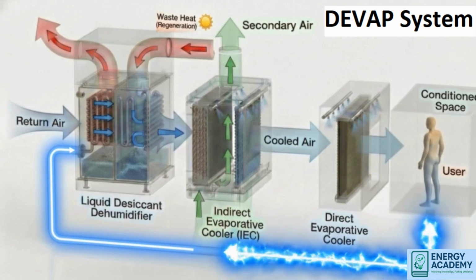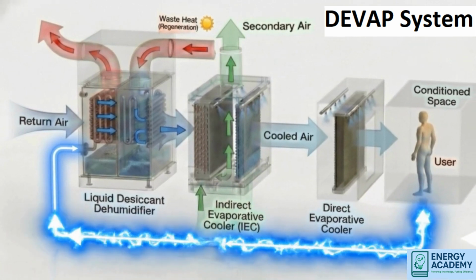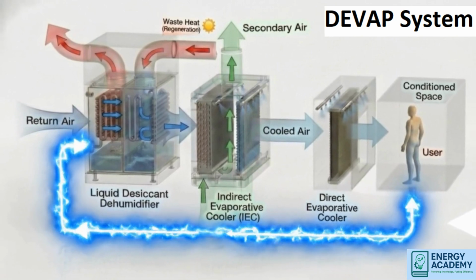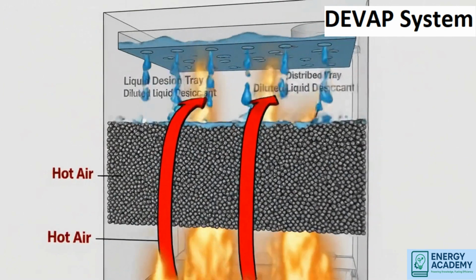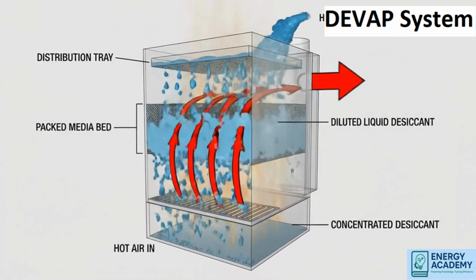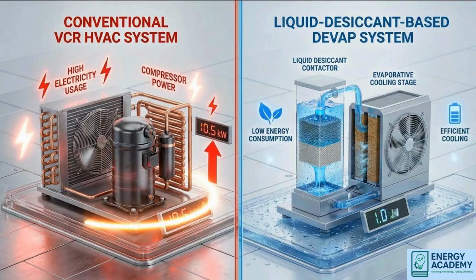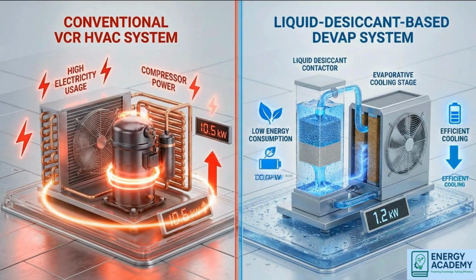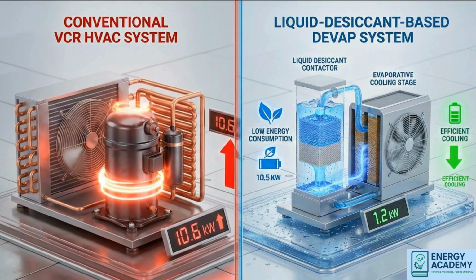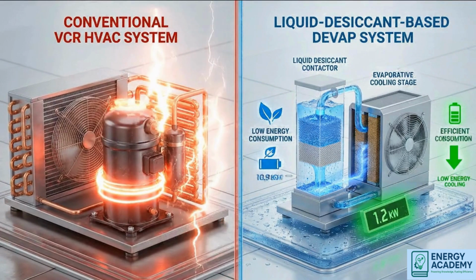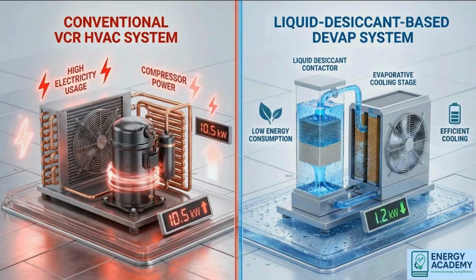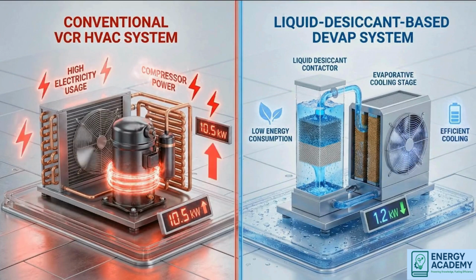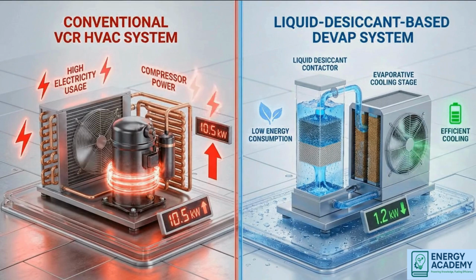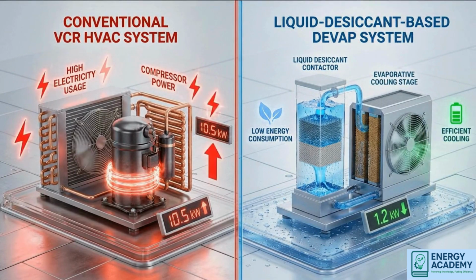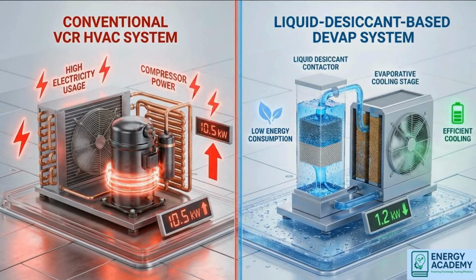Moreover, the indoor air recirculation further boosts the efficiency as it contains low humidity. And finally, to continue this process, the liquid desiccant is regenerated using waste or solar heat. If we compare, conventional HVAC systems rely heavily on compressors to remove humidity and temperature together, whereas liquid desiccant-based DEVAP separates these processes, removing latent heat chemically and sensible heat evaporatively, resulting in almost 50% energy savings.